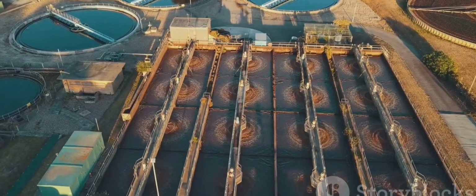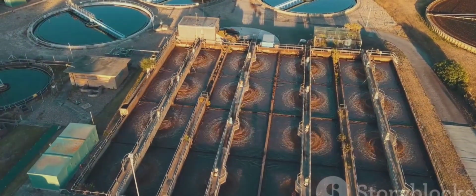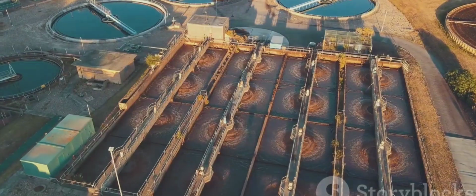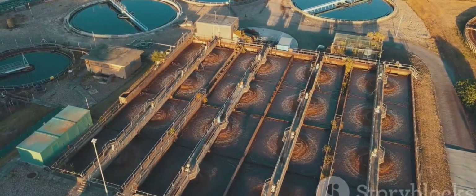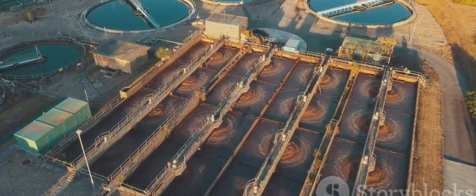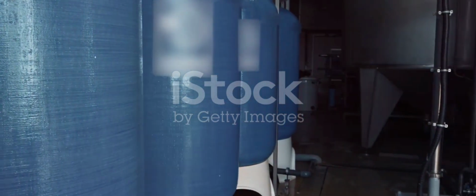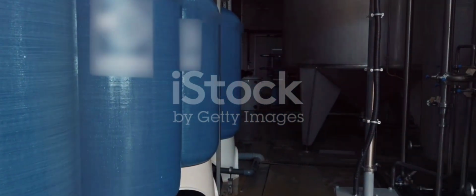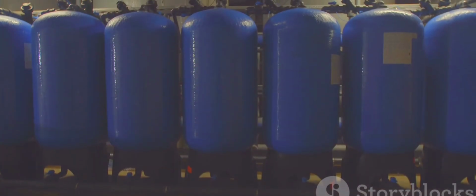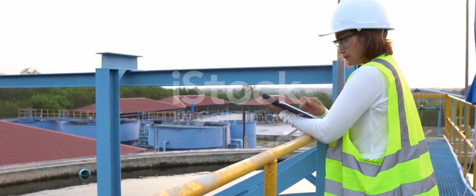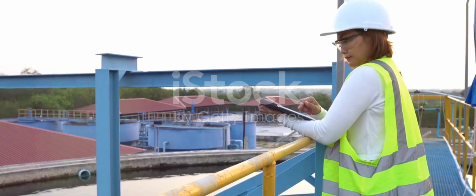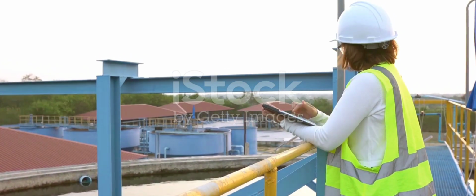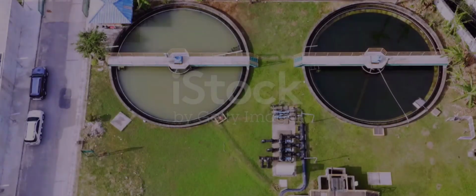Coagulation involves adding chemicals, like aluminum sulfate or ferric chloride, to the water, causing fine particles to clump together into larger particles. This is followed by flocculation, where slow mixing encourages these particles to form larger clumps or flocs. Important parameters to keep an eye on during this stage are pH levels, chemical dosage measured in milligrams per liter, mixing speed in RPM, and settling velocity.